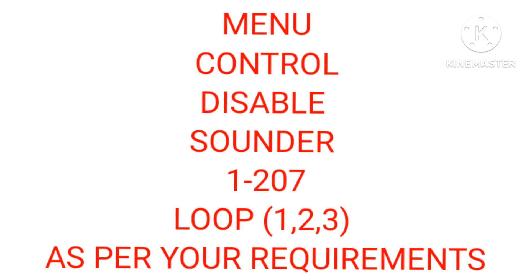By this method you can disable the sounders. If you want to enable them again, go to Menu, then Control, then Enable, then Sounders, then enter the parameters, and select the loop in which the sounders are located.